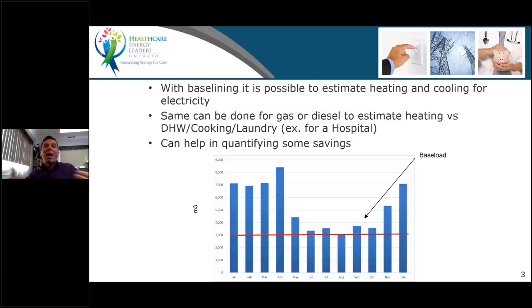And if you want to know how much can I save in heating, well, you take whatever's above that red line, and it will give you a total in cubic meters. And I'd say the first thing you should know is how it is roughly splitting between that base load and that heating. Because if you are 70% heating, you should really look at optimizing the heating component of what your boiler plant is providing. And if your base load is really significant, say 70%, then you should look at what's going on with my base load. Is it normal to be so high?